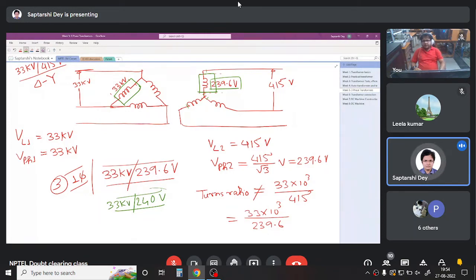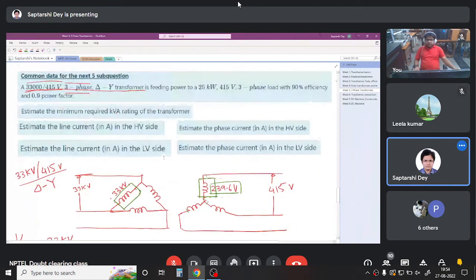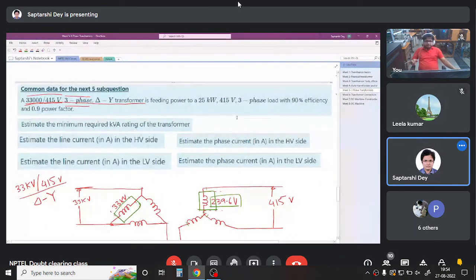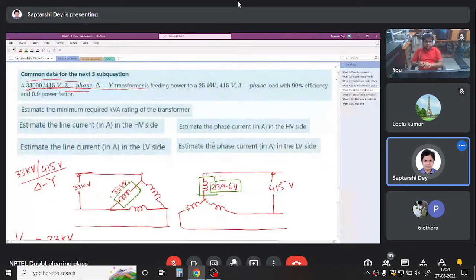So my point here is, when you have to find out the turns ratio for a three-phase transformer, you cannot simply do voltage by voltage. For the turns ratio, you have to look at it from the transformer point of view, from every winding point of view. Okay. So that being said, we can now look at the question.